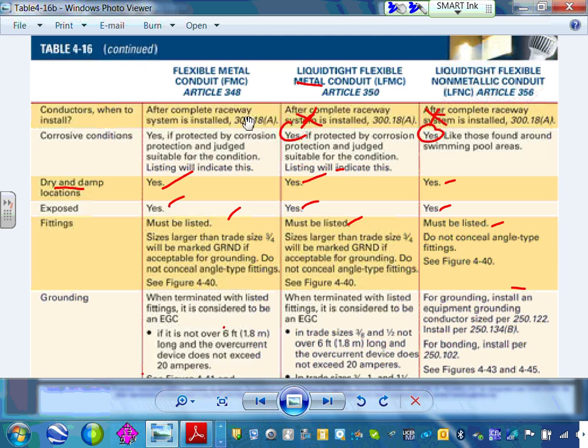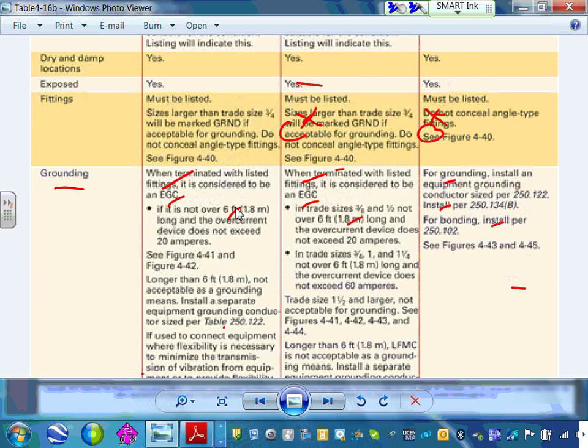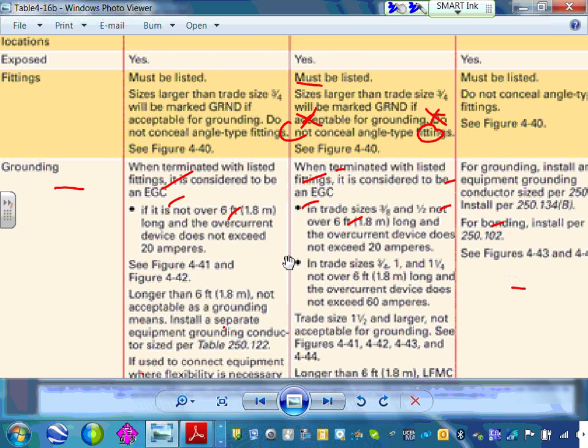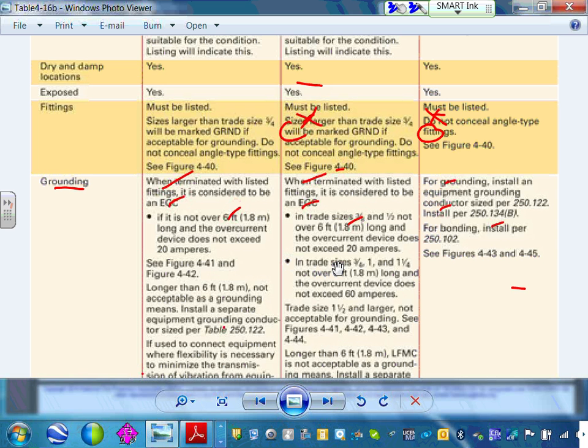Grounding. Look at the grounding though. For grounding, are they used? Can we use them for grounding? The answer should be no. But there are limitations though, you can use 6 foot. Here's a limitation where they can be used. Typically 6 foot, guys. Obviously, this cannot be used as a grounding, right? It's non-metallic. This guy has a limitation of 6 feet. What does it say? For fixture whips, 6 feet.